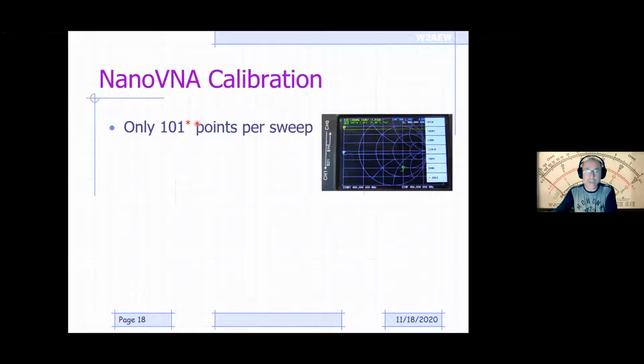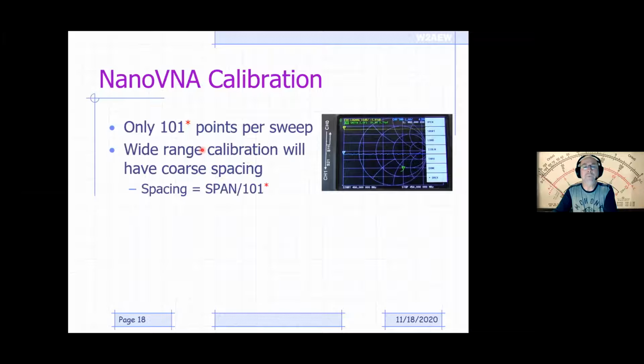Now I've got a little asterisk here next to that 101 points, and that's because some later versions of firmware made by some other third parties will offer the capability of doing more than 101 points. But for the most part, out of the box with the firmware that comes from the manufacturer, you're going to have essentially 101 points. So again, the calibration may have a fairly coarse spacing in terms of where the measurement points are.